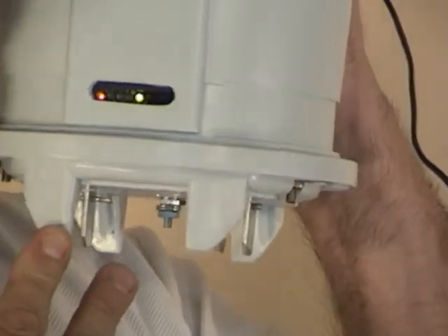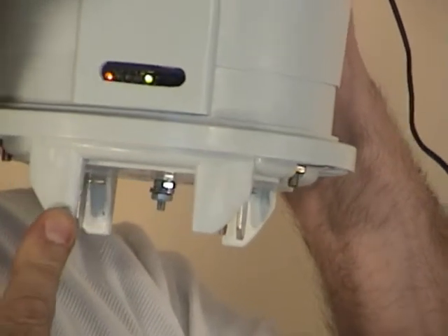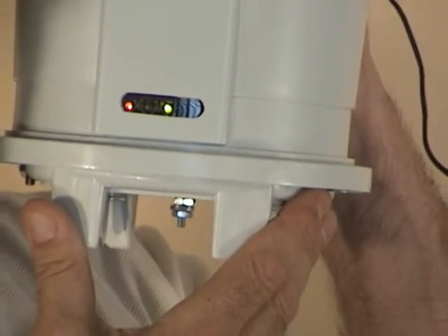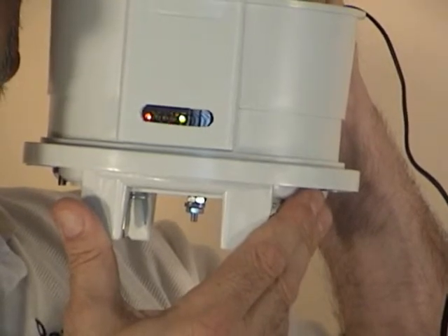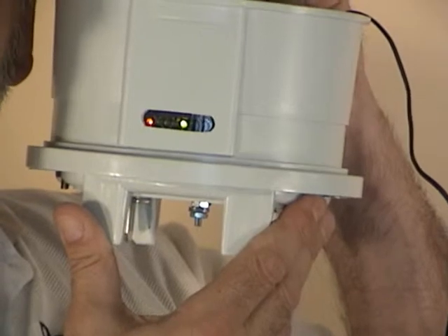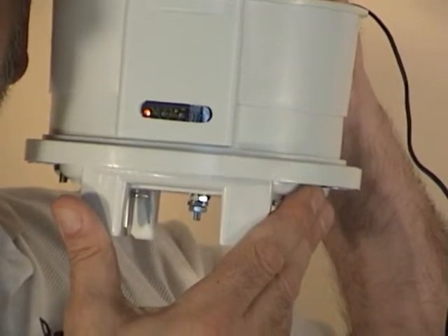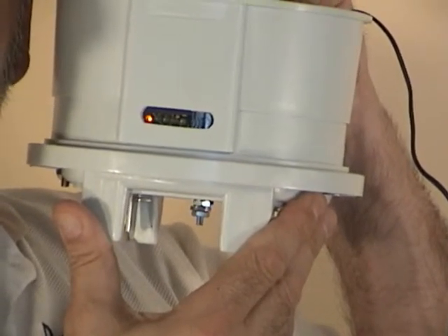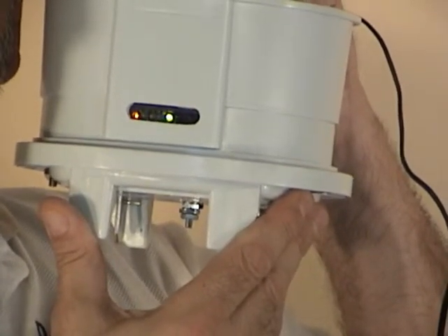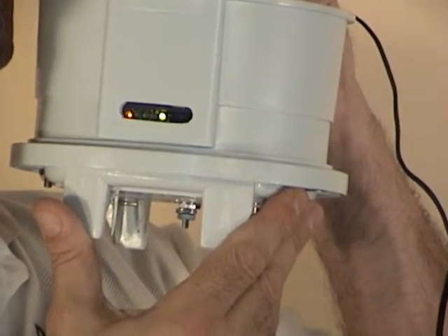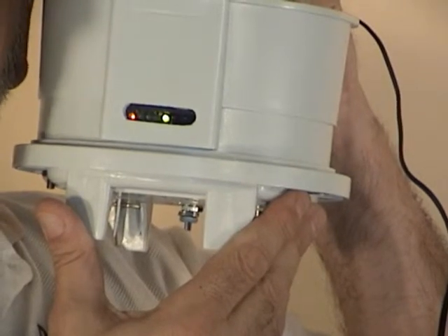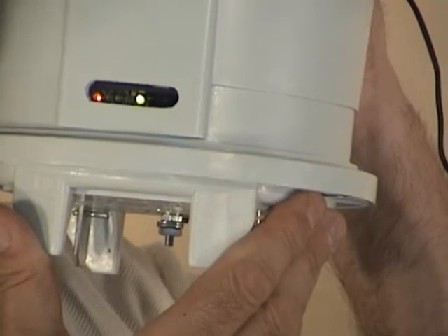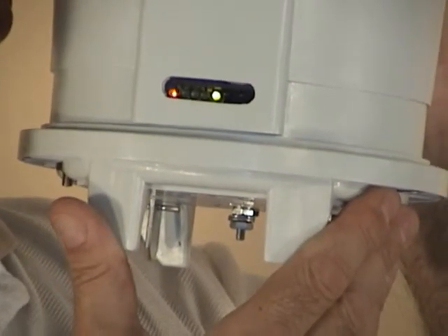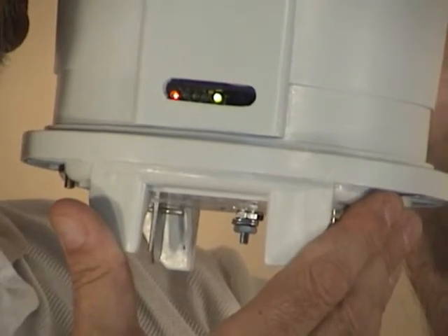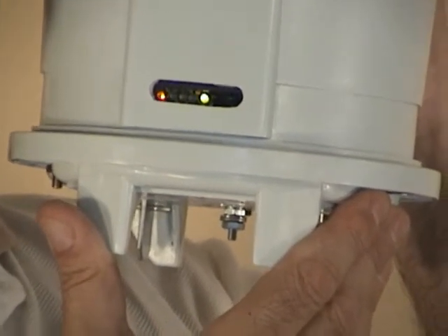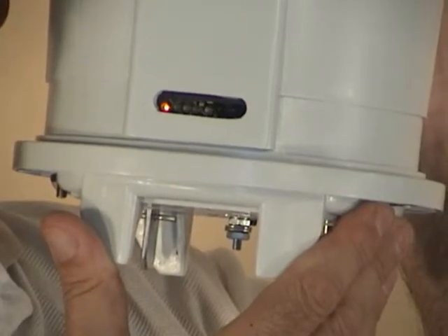So there's no chance of you forgetting to start or stop a unit. There's no chance of you accidentally erasing data. And you will know also the condition of the voltage as soon as you plug it in. There is a certain condition of blinking that will let you know that you are at the 125 volt level or higher, between 125 and 126, which is the last volt before you get out of spec on that 5% range we talked about. Also, the LED will flash to let you know if you're down between 115 and 114 volts, also at the last volt before you get to an out of spec condition. So as soon as you plug the unit in, you'll be able to tell if you're between 125 and 115, or if you're actually approaching that 126 or the 114. And that's all illustrated in color in the manual, so you know exactly what you're looking for.